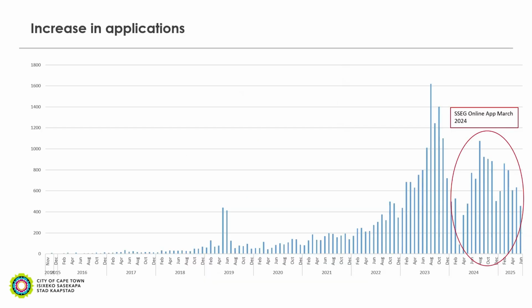The same table, table 2, we have for the dedicated customers. And as you can see here, these are obviously then the bigger supply, starting from 125 amps right up to 1,500 amps, which is typically the capacity up to 1 MVA with the corresponding limits.